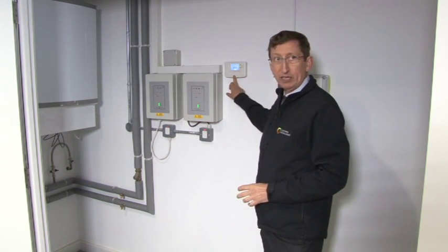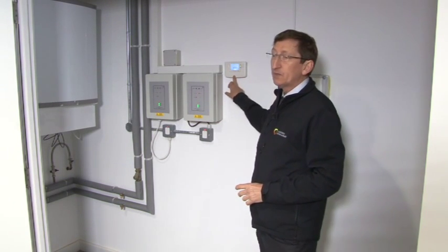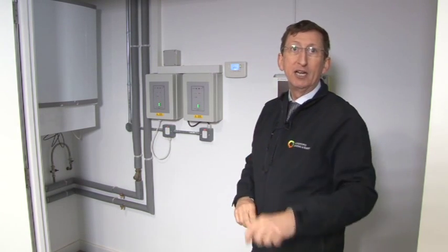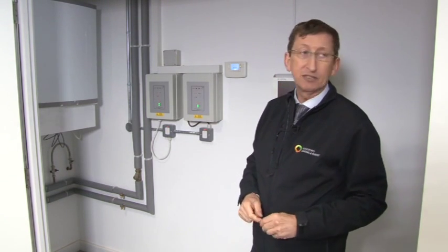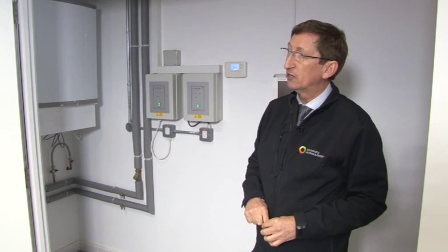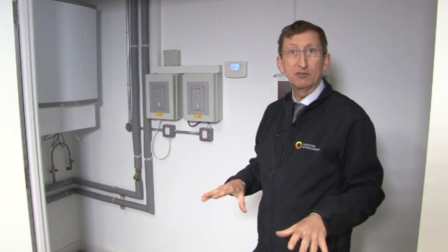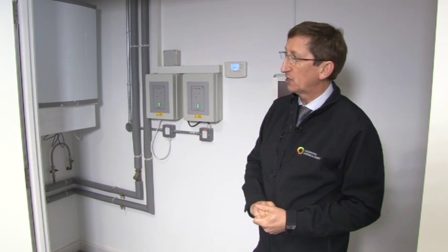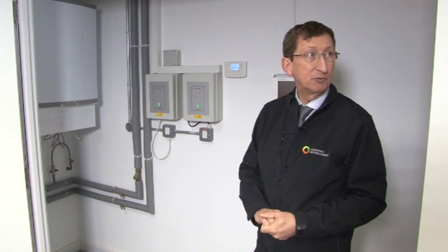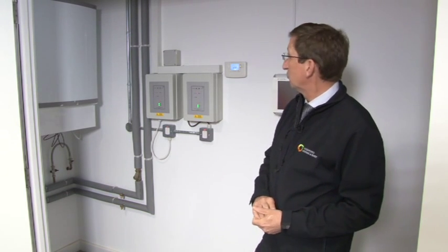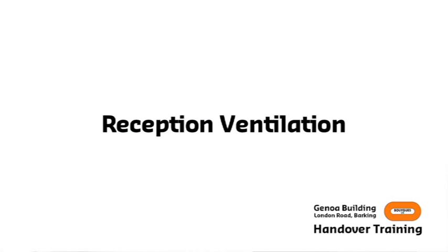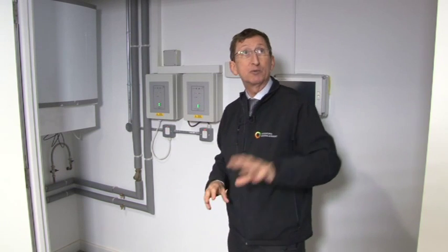Controlled by the time clock here, so it's on a time control. Okay, and there's also a thermostat located behind the concierge's desk, just looking at the temperature of the area. The individual radiators themselves then have got thermostatic radiator valves on them to control the temperature in those particular rooms.